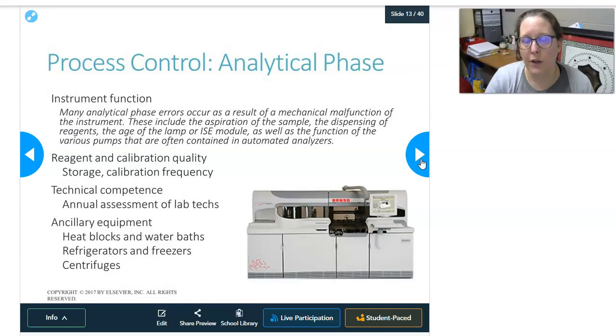Okay, so now let's move into the analytical phase. So instrument function is very important to the process control of the analytical phase. So many analytical phase errors will occur as a result of a mechanical malfunction of the instrument. So these could include aspiration of the sample, the dispensing of reagents, the age of the lamp, the age of the ISE module, the function of the various pumps that are often contained in the automated analyzers. There are a bunch of moving parts, a bunch of things going on, and something can go wrong at any time. You want to use proper reagents and calibrators and all that to maintain quality.